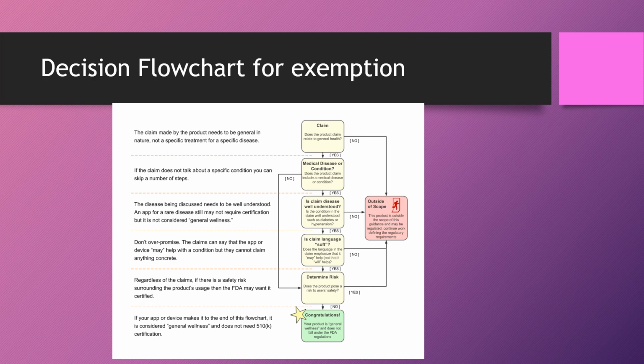Is the claim language soft? Now this is the key point. This gets to promising about what your app or device can actually do. Does it say that it's helping with monitoring and measuring, or does it make claims around actually diagnosing, preventing, or treating? This will determine if it falls under wellness or if it gets into the regulated category. So basically, the important thing to take away from this is that everything around whether or not your device could be regulated or fall into the wellness exemption category has to do with what is your labeled intended use, what is the risk, what is the technology, and how do you present it.